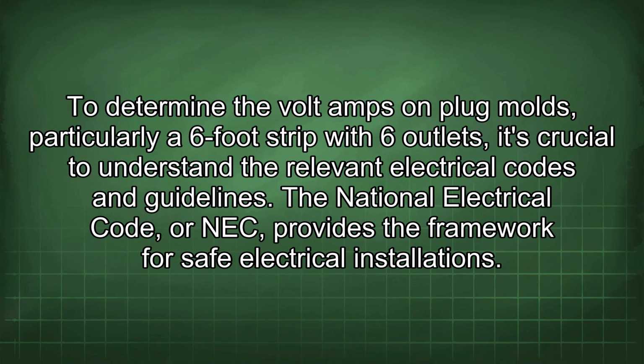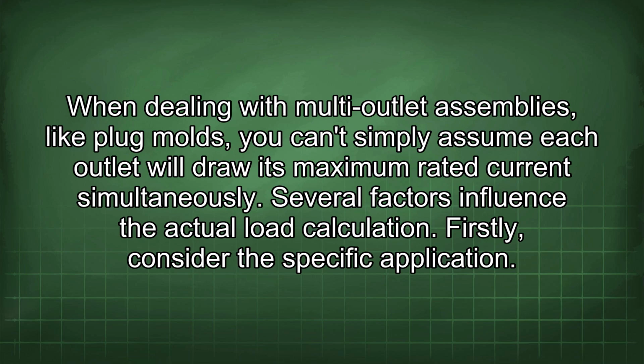To determine the voltamps on plug molds, particularly a 6-foot strip with 6 outlets, it's crucial to understand the relevant electrical codes and guidelines. The National Electrical Code, or NEC, provides the framework for safe electrical installations. When dealing with multi-outlet assemblies like plug molds, you can't simply assume each outlet will draw its maximum rated current simultaneously. Several factors influence the actual load calculation.